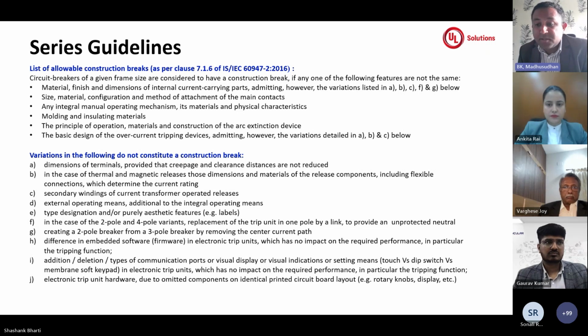And with respect to this, if all these constructions are similar, then you can declare that particular range as a single construction break. And also coming to the next, on the size, material, and configuration, the method of attaching your main contacts. So the design should be the same. If there is any variation within this, it will be considered a separate construction that you have to declare as an additional construction or a second construction. And also your integral manual operating mechanism should be the same. The materials and the physical characteristics should remain the same. If there is any deviation or any additional feature getting added, then you have to bifurcate that and declare it as an additional construction.